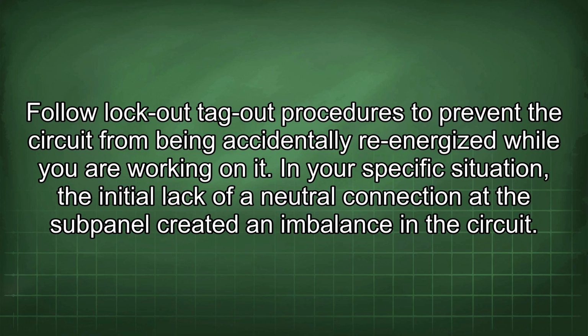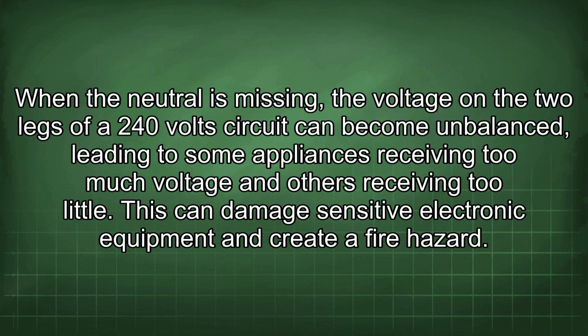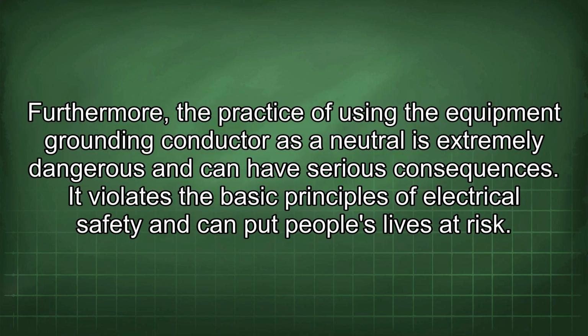In your specific situation, the initial lack of a neutral connection at the subpanel created an imbalance in the circuit. When the neutral is missing, the voltage on the two legs of a 240-volt circuit can become unbalanced, leading to some appliances receiving too much voltage and others receiving too little. This can damage sensitive electronic equipment and create a fire hazard. Furthermore, the practice of using the equipment grounding conductor as a neutral is extremely dangerous and can have serious consequences. It violates the basic principles of electrical safety and can put people's lives at risk.